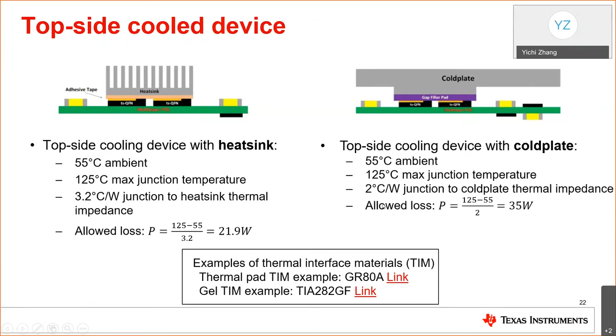And we do have some examples of thermal interface material you can use over here. And here I will quickly go over some of the advantage and disadvantage of each thermal solution with topside cooling device with the cold plate. So for the gap filler gel, it's excellent conformability and good tolerance in component height variance and thermal planarity. And then the disadvantage is it has a relatively high thermal impedance with gap filler gel.